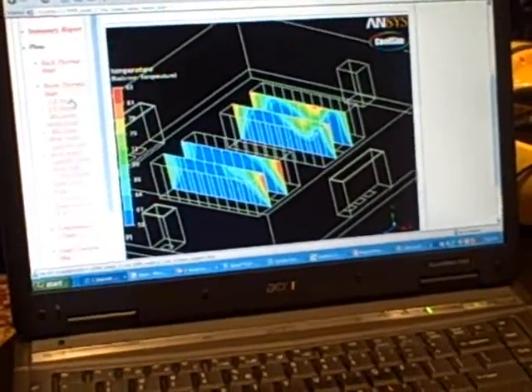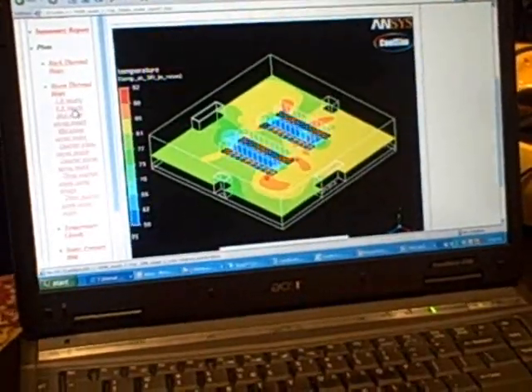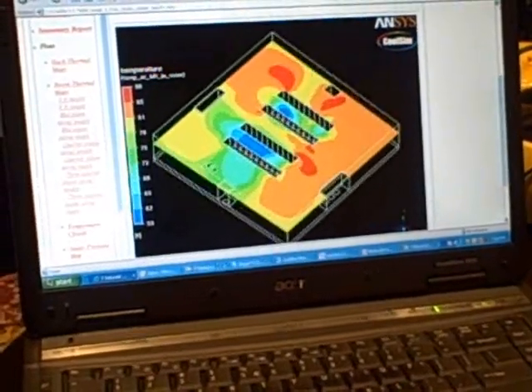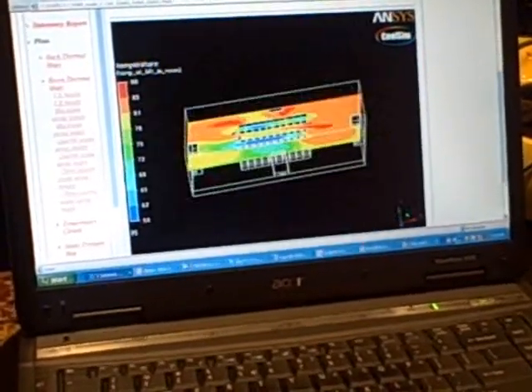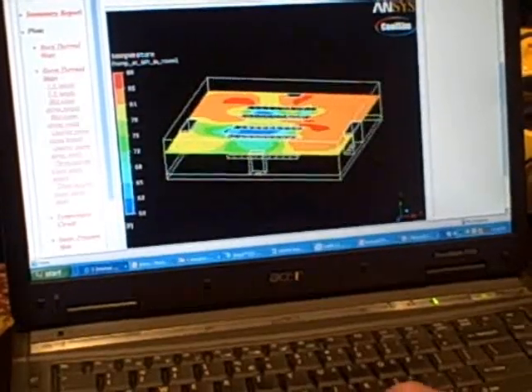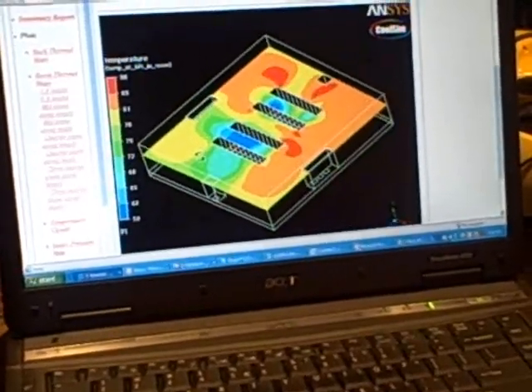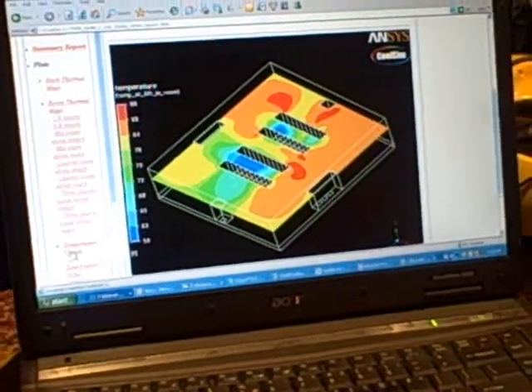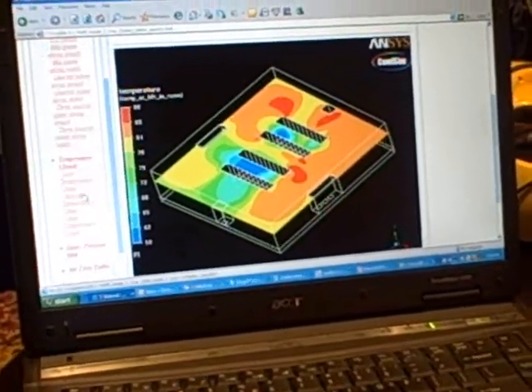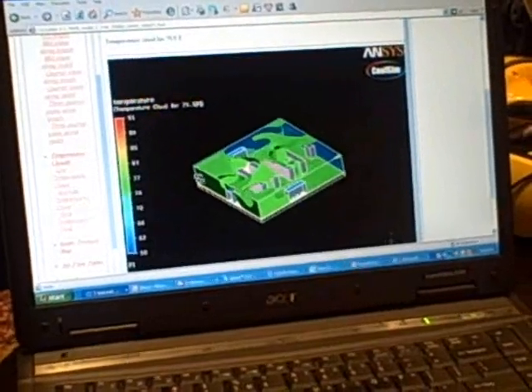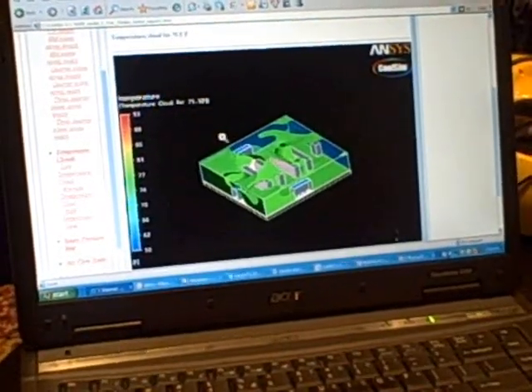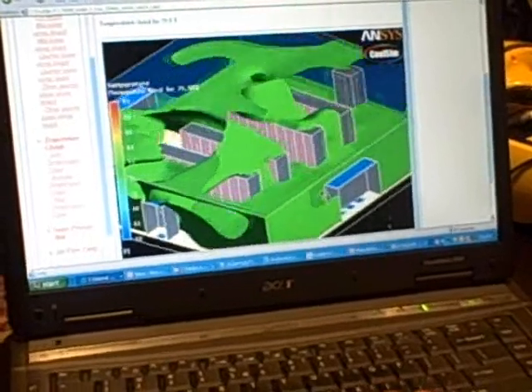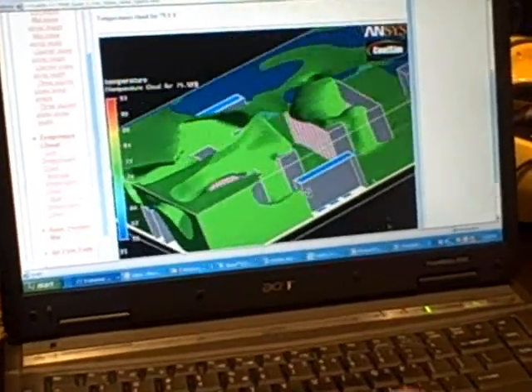I'm able to look at maps in the data center of temperature at specific heights. Here's a map at six feet. I'm able to manipulate view. I'm able to make very high-quality output images of this, including JPEG and EPS, as well as VRML outputs. I'm able to look at temperature clouds, such as the average temperature cloud in the room. This is an isothermal surface of constant temperature, showing us where the areas of this temperature, 75.5 degrees, are.